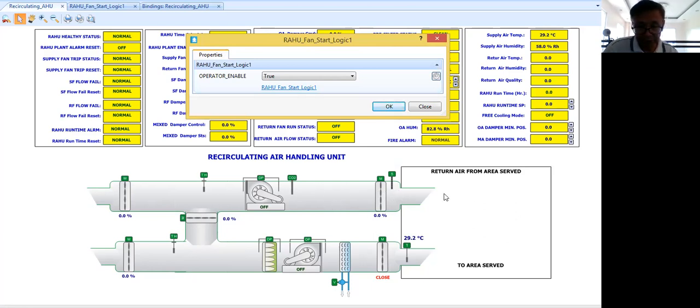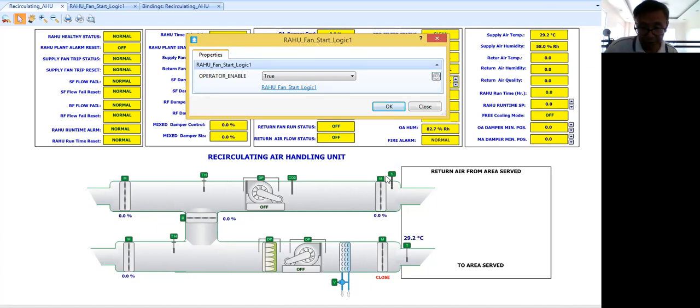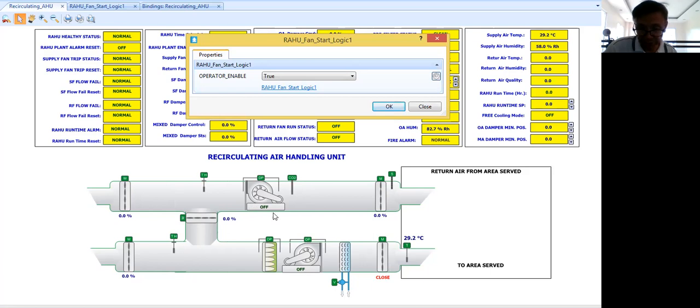My control logic program will try to open first the necessary dampers. Then when it is open, then that's the time after some time delay I will be starting my fans.